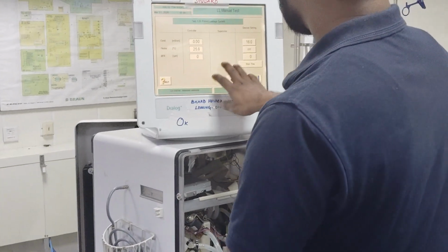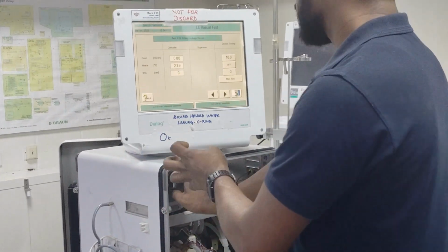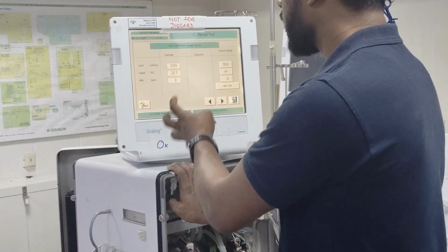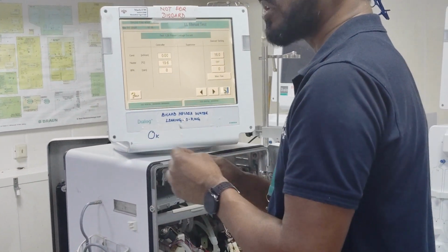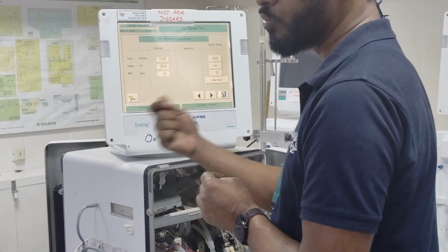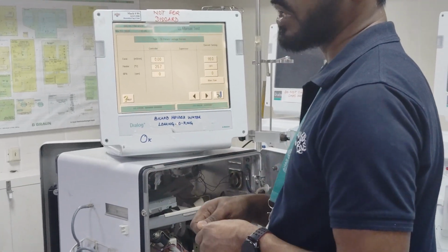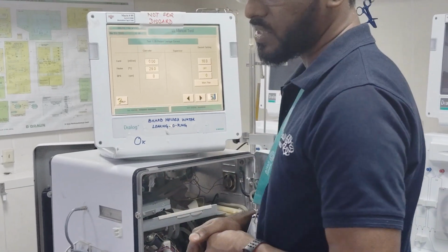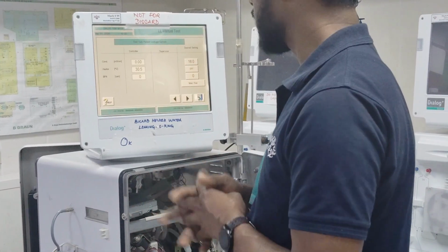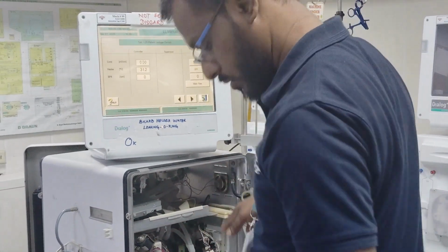Patient leakage current is something between the heater and this one. You can check how much leakage current is there at the output from the heater using a multimeter or a safety analyzer. You have a safety analyzer for checking that.